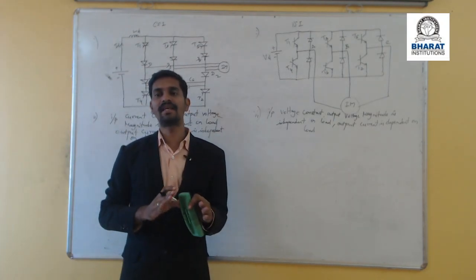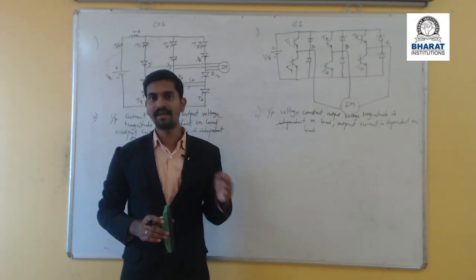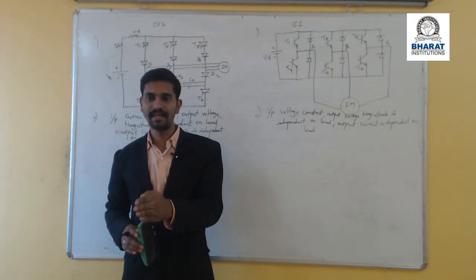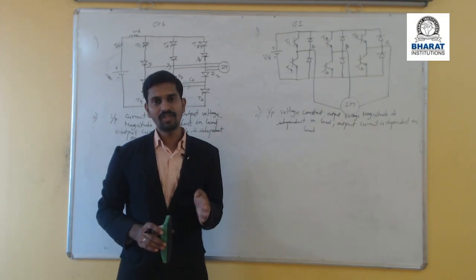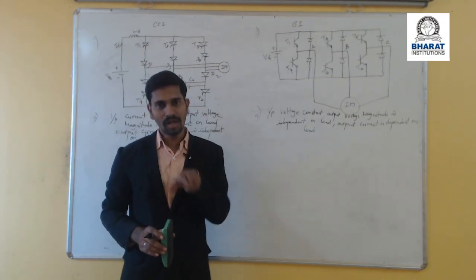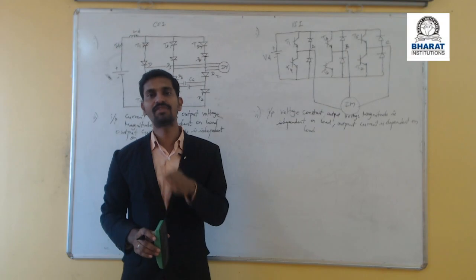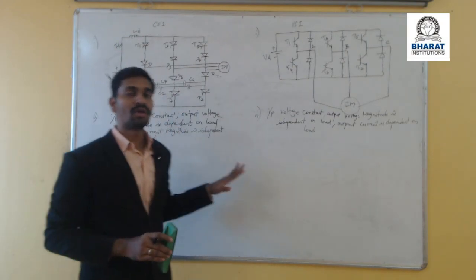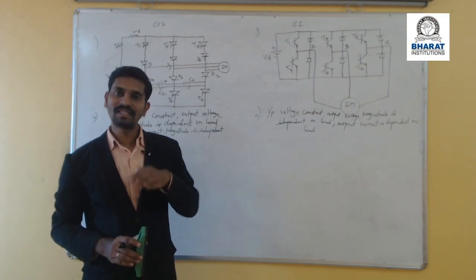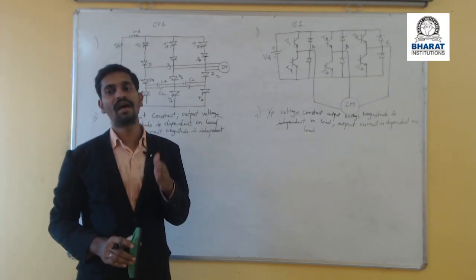This happens in a closed-loop control system. We sense the speed, and based on the speed error — whether positive or negative — the reference frequency is set with the help of a controller. Based on that reference frequency, the appropriate firing angle of the inverters is given, and based on that firing angle, the variable frequency and variable stator voltage are achieved. Once the frequency and stator voltage are varied, the speed of the induction motor is controlled.